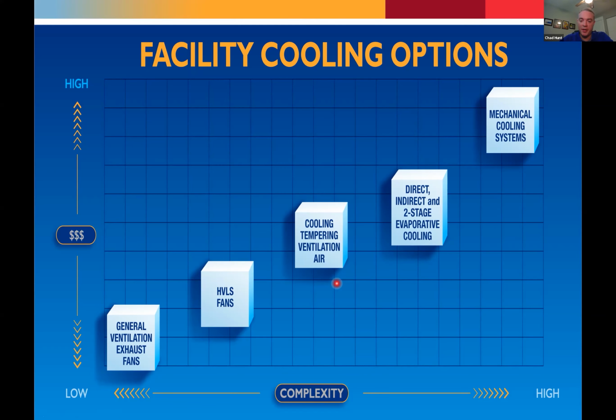So what Cambridge did is we actually created a two-stage evaporative unit for the Midwest, where we don't get the benefit of a direct evaporative option. And we operate our indirect unit most of the time. And we have our direct component of the two-stage tied to a humidistat.